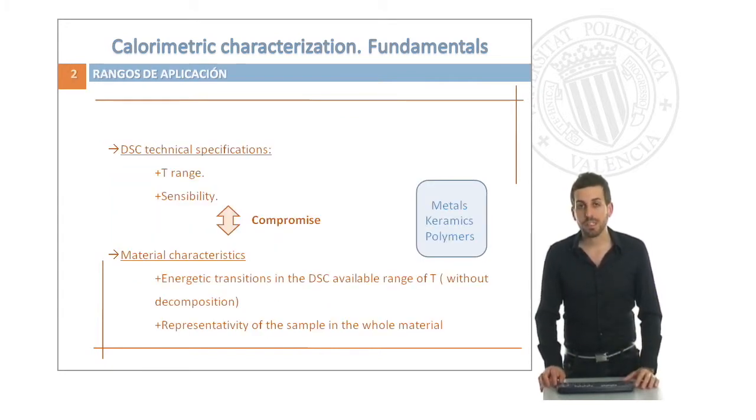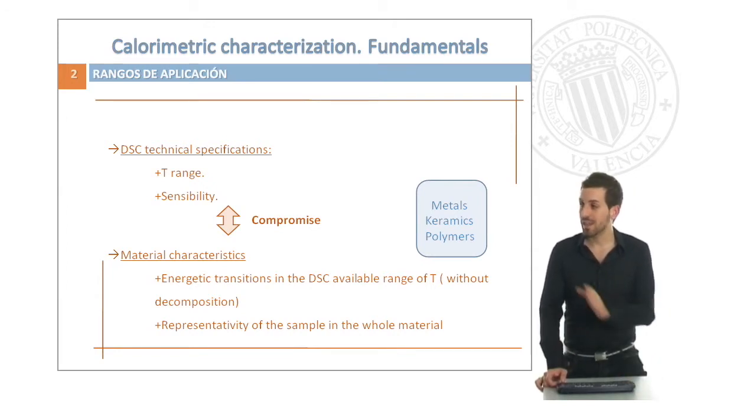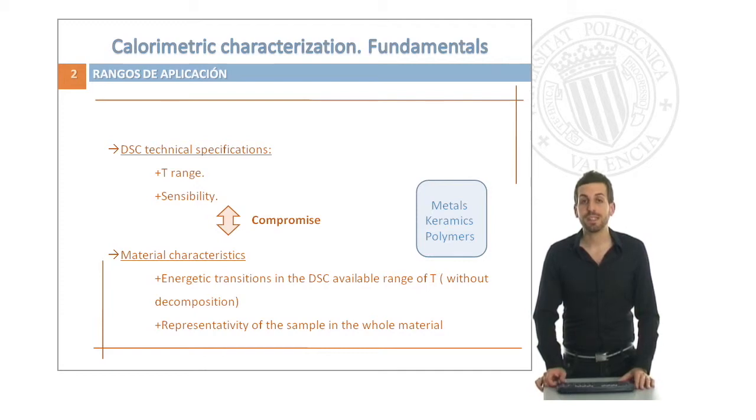When we are thinking about our experiments, we have to take into account two different features. First, we have to know the DSC technical specifications: the temperature range available for our DSC and the sensitivity of our measurement. On the other hand, we have to know if the energetic transitions of our material are available in our DSC temperature range, and it's very important to know if the representativity of our sample related to the whole material is representative enough.